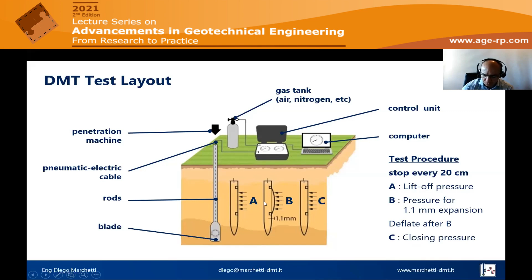To look into this mechanism, let me repeat it with this slide. So we push the blade into the soil. The pressure of the soil, which are the red arrows, flatten the membrane against what is behind it, and the contact of the membrane is on. Now the operator inflates, and when the pressure of the gas is in equilibrium with the pressure of the soil, the membrane starts to expand, and the signal of the contact membrane goes off.